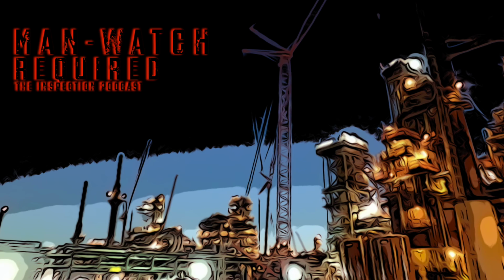There's manually operated valves too, pneumatic valves, control valves, things like that. Not quite as common at a PSV, I would say. It's usually a gate valve type of thing. But yeah, you'll see a program in place verifying that it is car sealed open. And that's something ABSA will audit. I've been involved in that once before at a new facility, and that was one of the things they wanted to audit. They actually checked the tagging board, made notes on a few, and went out and did verify that they were car sealed or weren't. So that's something they will look at, and it is important too, right?